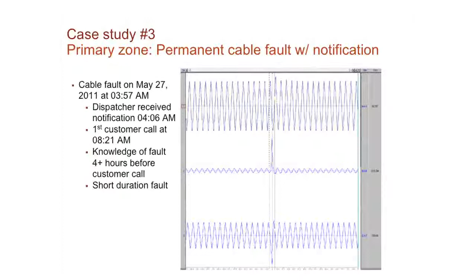I was just trying to show what we can do on permanent faults. The value here is with that information and the deployment we had, we could tell them with the short duration - because of that finer resolution of how long the fault was - that a fuse interrupted it, and what size. In many cases they confirmed, and we have a report we go through every 2 weeks and see like we're spot on or we missed one. But we'll give an estimate of, hey, we think that's a 65 amp fuse. We think that could be valuable information if they know ahead of time what size fuse blew.